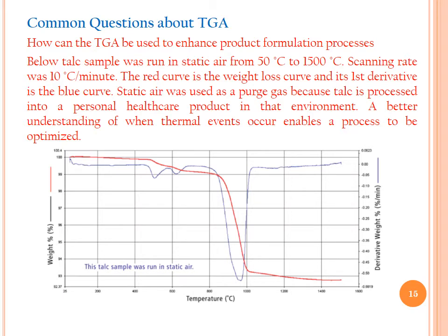So another question about the TGA: How can the TGA be used to enhance product formulation processes? The below talc sample was run in static air from 50 to 1500 degrees centigrade. Scanning rate was 10 degrees per minute. The red curve is the weight loss curve, and its first derivative is the blue curve, as clearly seen from the graph below.